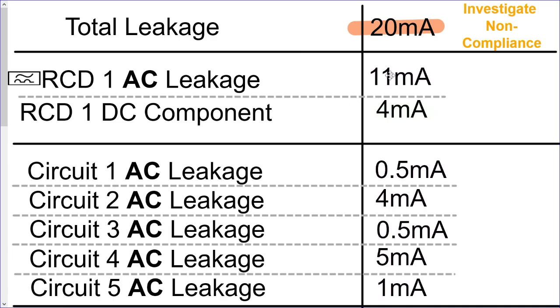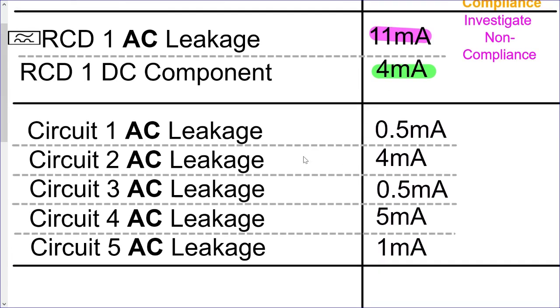Looking at RCD1, the AC leakage on that RCD was 11 milliamps. So we're going to need to carry out further investigation on that side of the board. The DC component was 4 milliamps, so that's less than the 6 milliamps that were allowed for that type A RCD, so we're quite happy with that, so we don't need to investigate the DC components.